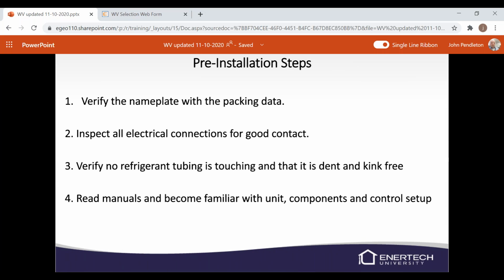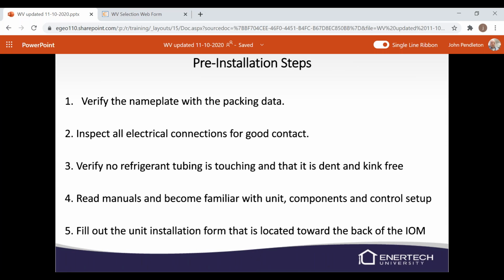Pre-installation, make sure you've got the correct unit, whether it's an 040 or 060. I hate for you to install the 040 and you need an 060 and then it won't keep up. So make sure you've got the proper unit and all the pieces that come with it. Inspect the electrical connections. Make sure you've got good contacts, especially the main power lugs. They're a screw fitting or a connection, and sometimes those can get a little loose in shipment. Verify there's no refrigerant tubing that's touching each other or has any kinks or anything like that in it.